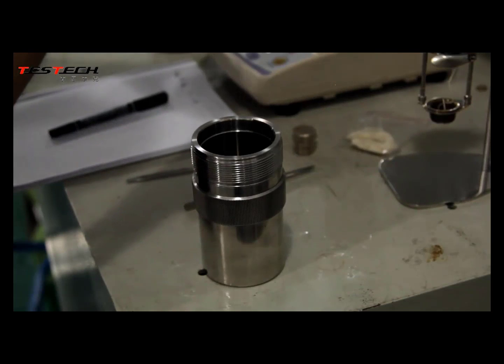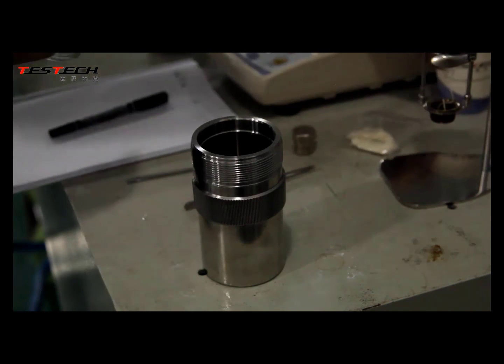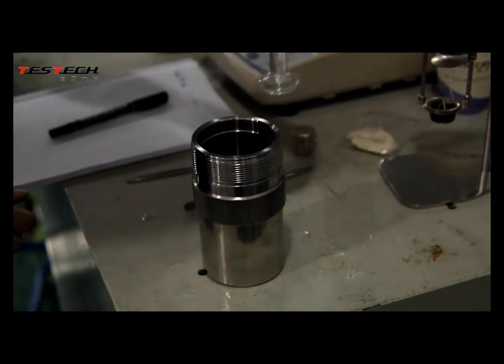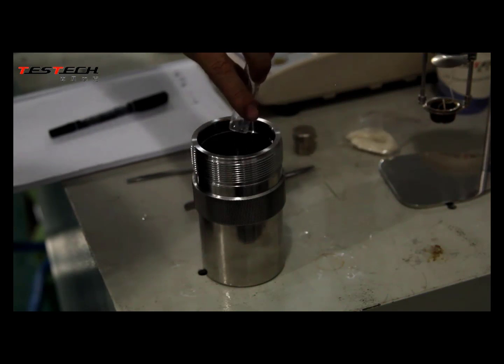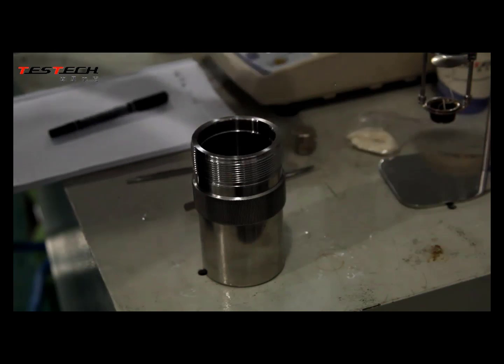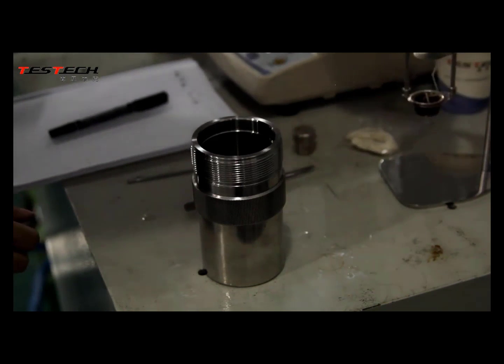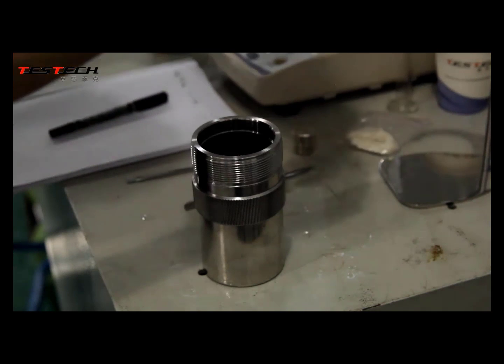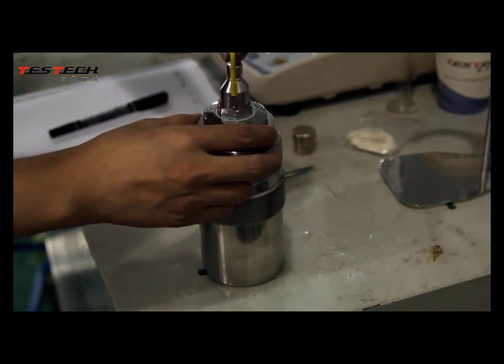That's the flask which will effectively accept the explosion from the test. It's quite substantial. That's benzoic acid being applied inside the flask at the same weight as the product. So if it was a gram of product, then it would be a gram of benzoic acid.